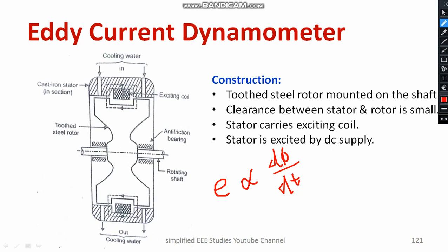There should be a closed path for eddy current. Regarding the eddy current dynamometer arrangement, we have a toothed steel rotor — it is made up of steel material and is a conductor. On the top and bottom sides, there is an exciting coil. Current passes through the coil, generating a magnetic field. We also have a rotating shaft. Our ultimate goal is to measure the torque and angular speed, thereby computing the shaft power.